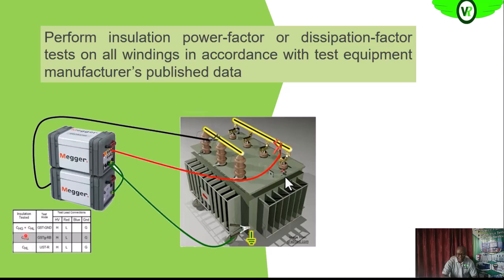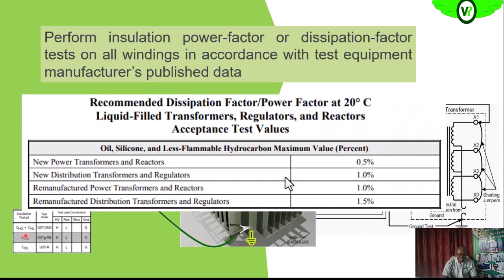You can also look at the description below for a link to our earlier training on power factor testing or turn ratio testing on transformers. So here are some of the expected results if none is recommended by your manufacturer or specified for your facility. You can also use this as a guide: for new transformers and reactors 0.5%, for new distribution transformers and regulators 1%. Then transformers that have been worked on or reactors that have been worked on, 1% is also okay. So we use these as a guide.